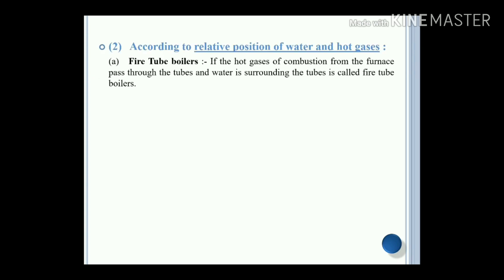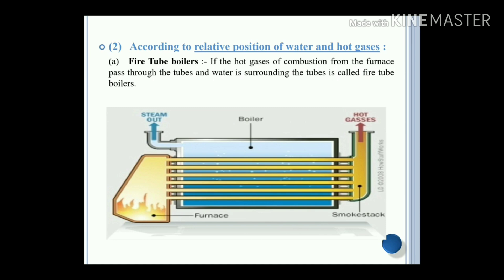According to the relative position of water and hot gases — fire tube boilers: if the hot gases of combustion from the furnace pass through the tubes and water surrounds the tubes, it is called a fire tube boiler. In simple terms, if hot gases are inside the tubes, that kind of boiler is said to be a fire tube boiler, and the surrounding portion of that pipe will be water.